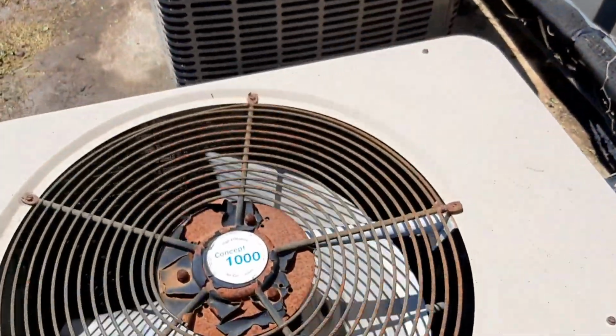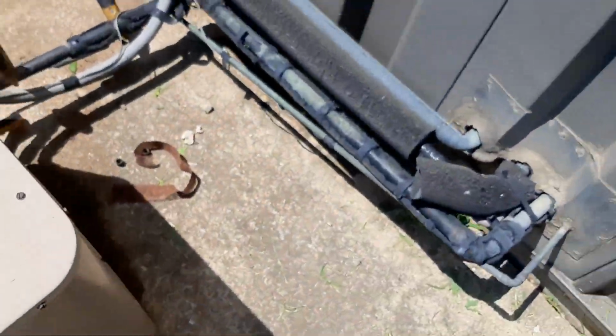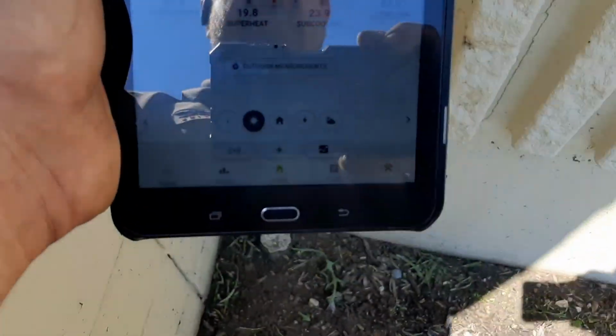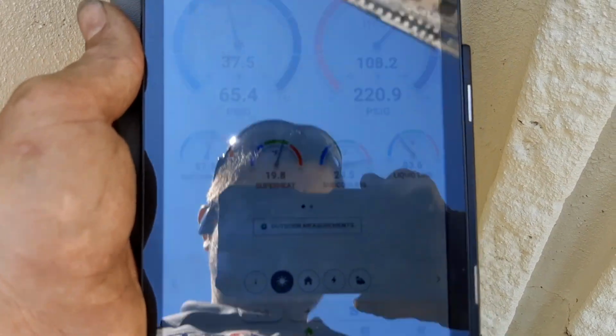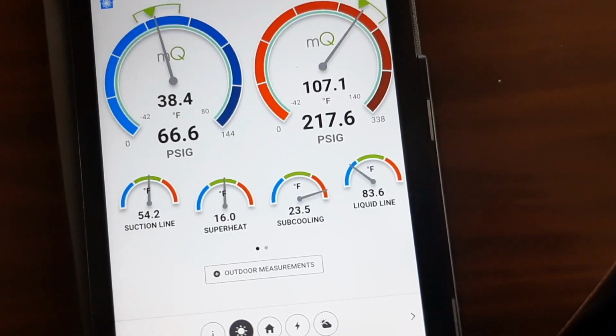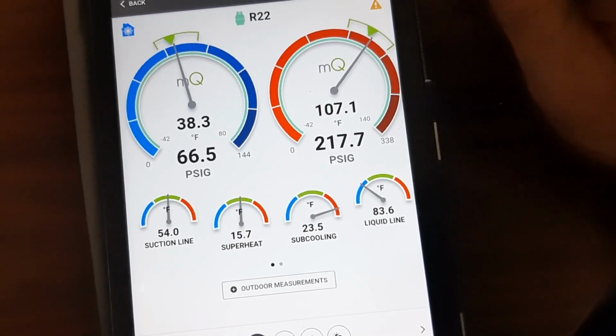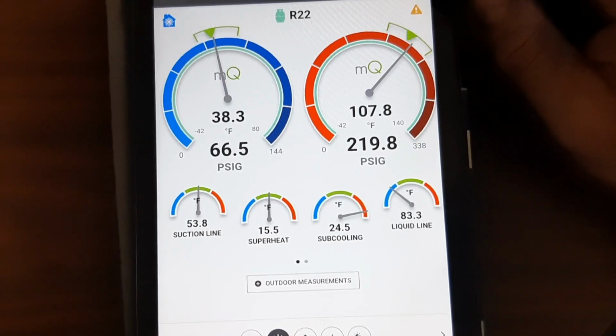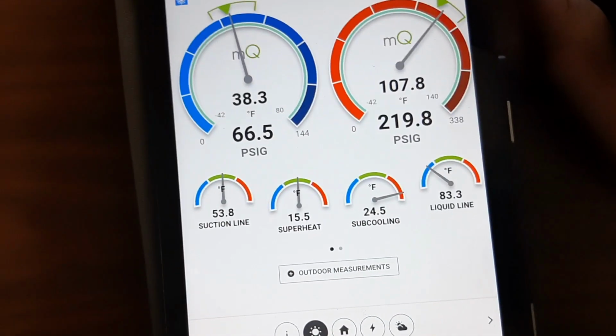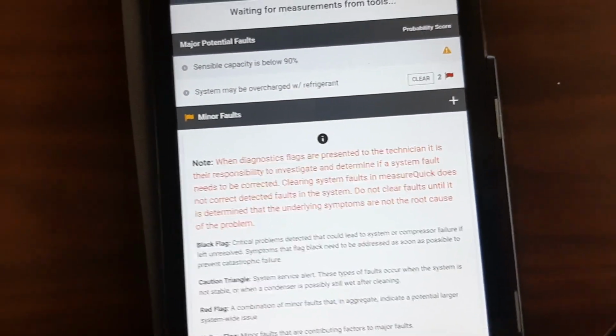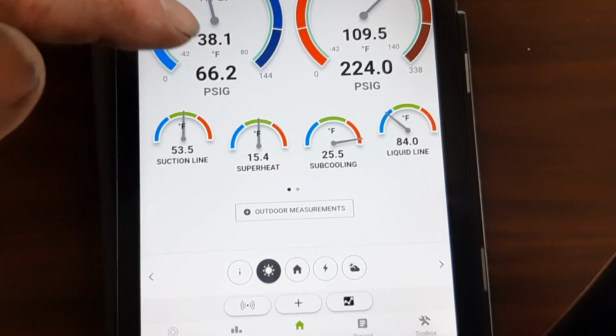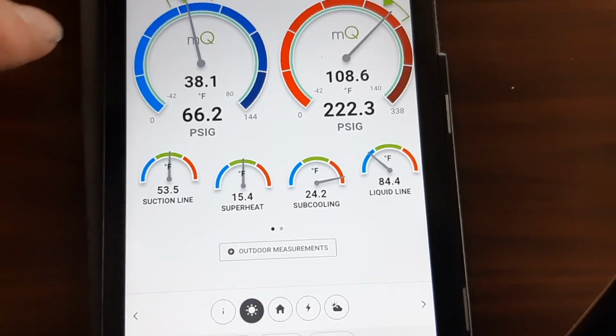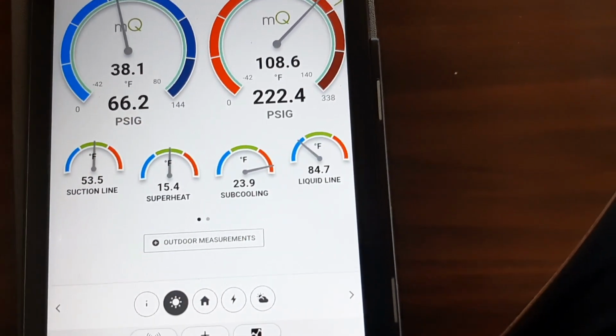I know this coil's clean. It's high efficiency. Well, you know, I'm running reasonable superheat. You can go inside and get you guys a look, but my subcooling's through the roof. So my subcooling's up. I think this one's a TXV too, but my pressure's up too. It's almost like it's slightly restricted. Measure Quick says overcharged, but I'm wondering if it's not. If my metering device was restricted and then they dump charge trying to get that suction pressure up, not to mention my airflow issues.